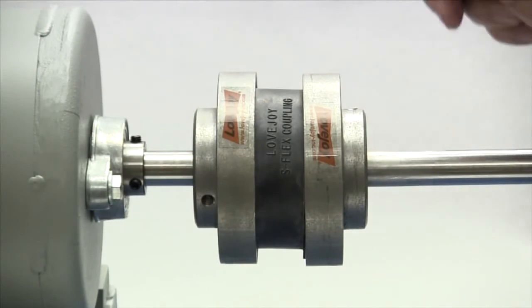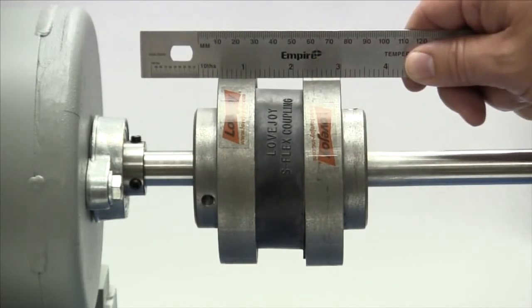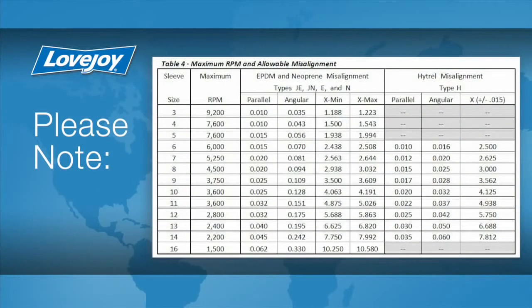To check the basic alignment, start by laying a straight edge across the major diameter of the flanges. The maximum allowable parallel offset should not exceed the amount for your particular coupling size found in the installation guide and shown here.